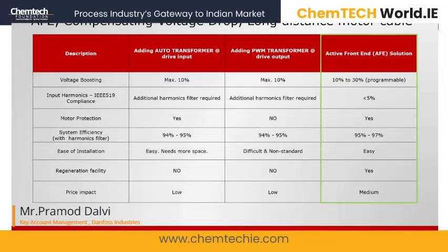But with the active front end, you can still maintain the efficiency at 95 to 97% and still have the harmonics below 5%. And if your application is regenerative, which in this case it wasn't, then you get the additional benefit of regeneration also. There is a low impact on other solutions, but there is a high impact on the efficiency side, and the price impact on active front end is medium, you can say.